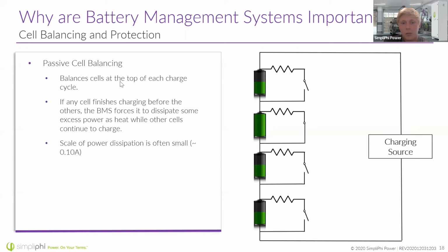Is there a limit to the number of 48-volt batteries that can be paralleled for capacity? If you're using Phi batteries, you can parallel as many as you need. I have seen over 100 batteries in parallel when it comes to Phi. With SimpliPhi, you can parallel up to 75, because you need to make sure the communications line is able to transmit signal all the way to the end of that line. So based on the communications need, you can only parallel 75 SimpliPhi batteries, which is still, quite frankly, a whole lot of batteries.